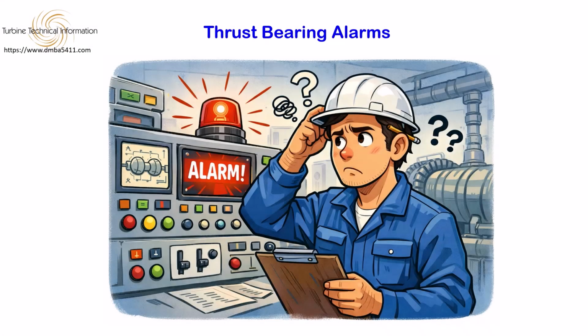The false alarm on your thrust channel. A thrust channel alarm doesn't always mean your bearing is failing. In some cases, the hardware is perfectly healthy, but the system was incorrectly set up during commissioning.